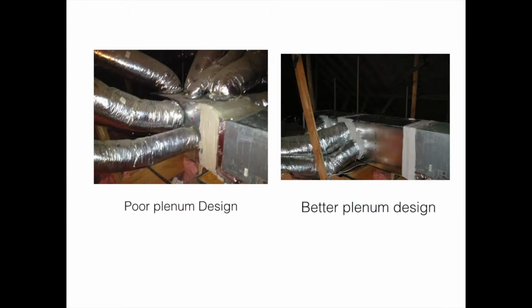So now we're going to take a look at some common problems that we've seen in the field, and hopefully these descriptions can help you avoid these problems with your own buildings. Here are two pictures of plenum design. The picture on the left shows all of the ducts really close together and the larger ducts at the end of the plenum, which essentially rob the ducts in the beginning of any airflow that they might be getting. The picture on the right shows space left at the end of the plenum and space before the plenum. This is still not the ideal plenum design as the ducts are too close together, but it is definitely a start on making the air distribution better.